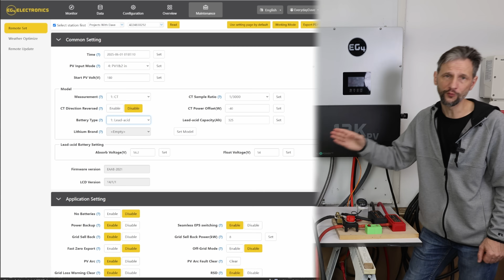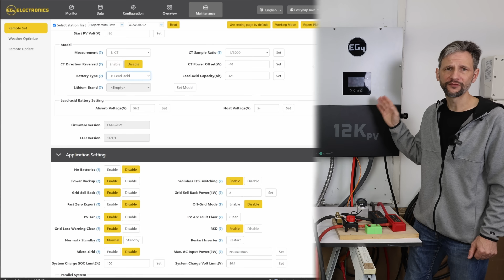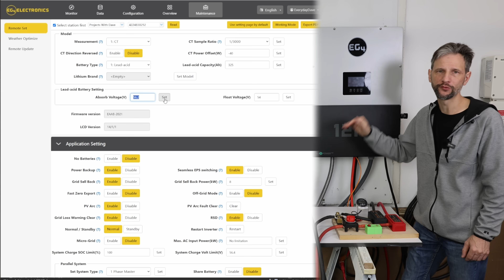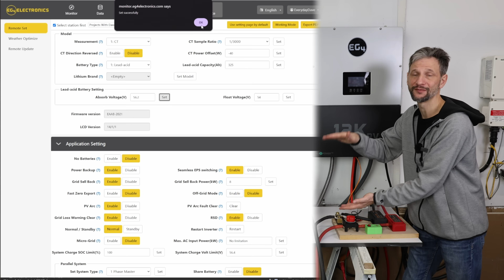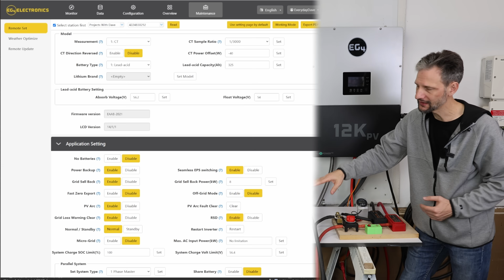The spec sheet calls out a boost or charge voltage of 14.4 volts, and we have 4 in series, which would be 57.6 volts. For the inverter, this is the absorb voltage, and I'll set that to 56.2, which is equivalent to about 3.5 volts at the cell level. And that should give us some margin for when the individual batteries are not in the exact same charge state. I don't want to overcharge one of them and have it shut down, disconnecting my series setup.